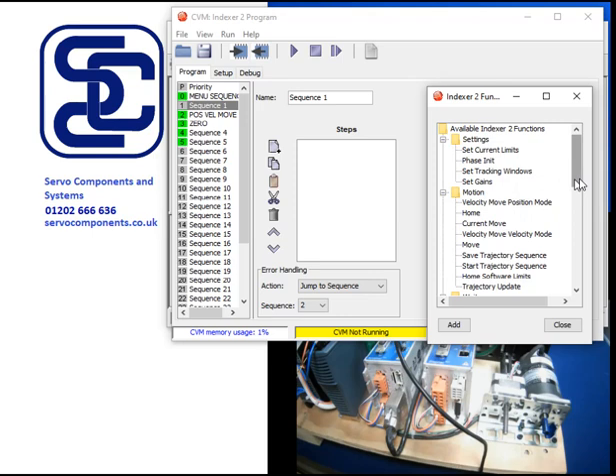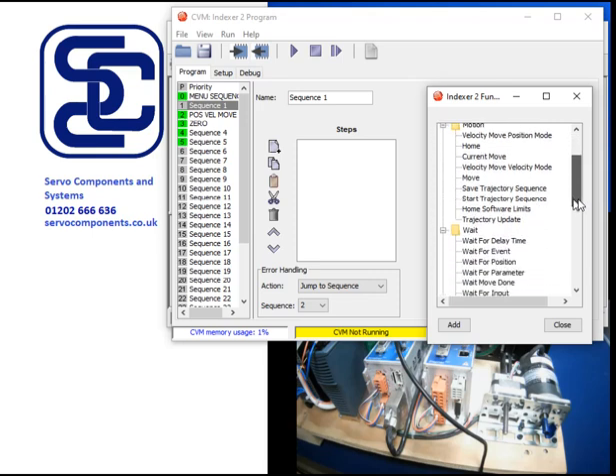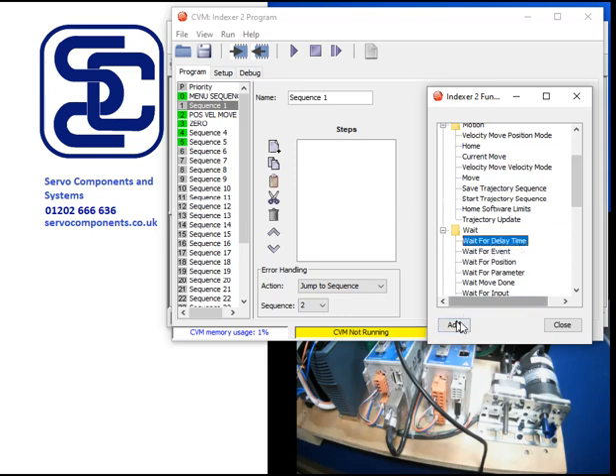If we do that on power up, then we need to give some time to allow the logic to actually power up and get initialized. So the first thing I would normally do is add the time delay at the beginning. So I wait for time delay here and add.